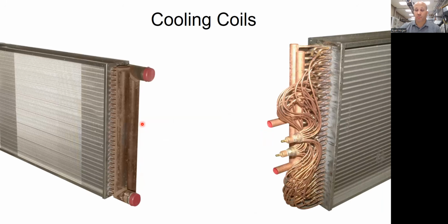So knowing if it's chilled water or not chilled water is going to make a decision on what type of path you go down in terms of recommending solutions. If it's a chilled water air handler, your cooling coil is going to be different. Everything else could be exactly the same, honestly. Drain pan, fan, heating system, dampers, all of it could be identical. The cooling coil is the only thing where you'll be able to tell if it's chilled water or not chilled water.